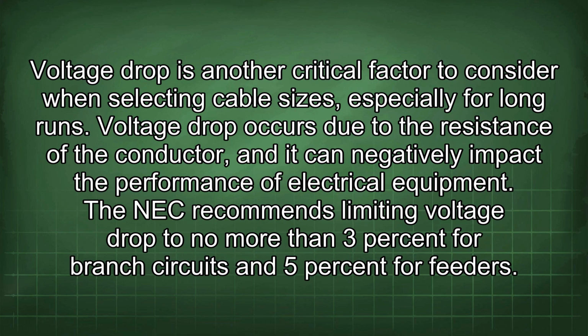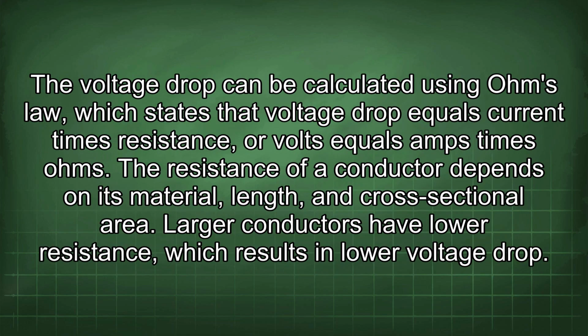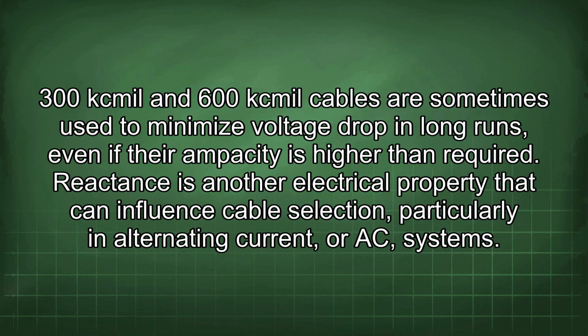Voltage drop occurs due to the resistance of a conductor, and it can negatively impact the performance of electrical equipment. The NEC recommends limiting voltage drop to no more than 3% for branch circuits and 5% for feeders. The voltage drop can be calculated using Ohm's law, which states that voltage drop equals current times resistance, or volts equals amps times ohms. The resistance of a conductor depends on its material, length, and cross-sectional area. Larger conductors have lower resistance, which results in lower voltage drop. 300kcmil and 600kcmil cables are sometimes used to minimize voltage drop in long runs, even if their ampacity is higher than required.